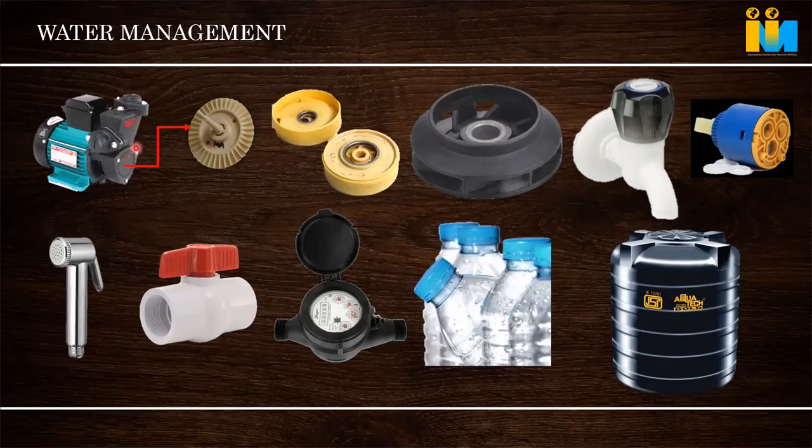This is a normal monoblock pump. In some of the small pumps, even plastic is used. Basically, Noryl is used. In most cases, filled Noryl, 20 or 30% filled, which can go up to an operating temperature of 135 degrees continuous use temperature, and has the least moisture absorption property, just 0.1. Moreover, it has very high dimensional accuracy because it is amorphous. So it has a mix of properties of all the things. That's why Noryl is used. These are all pump parts.